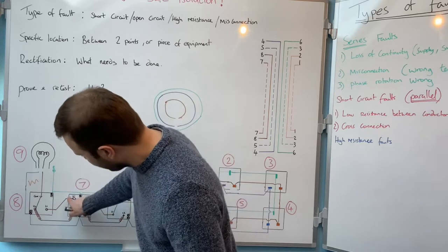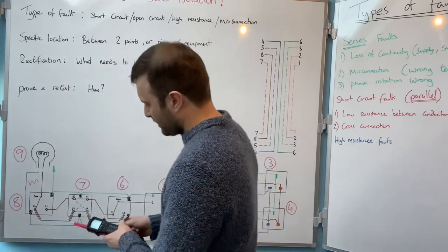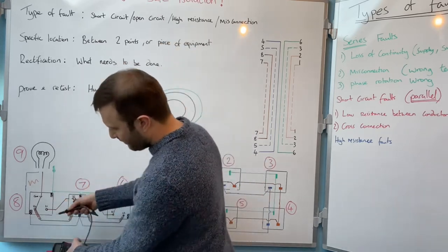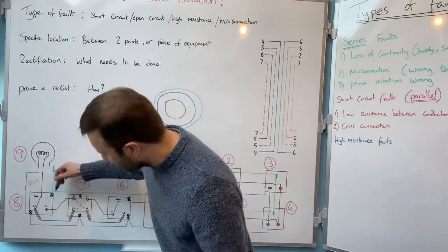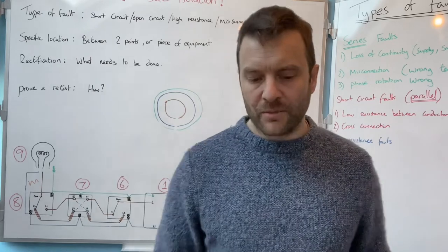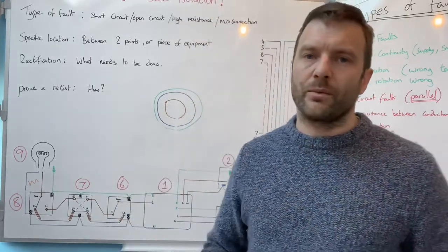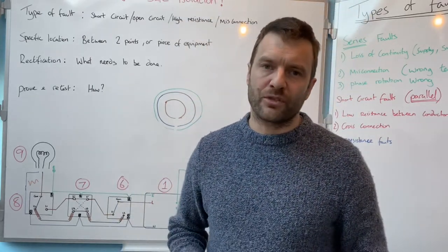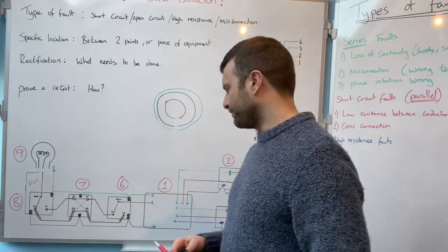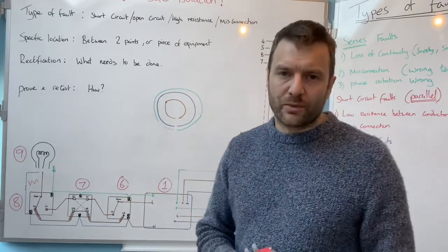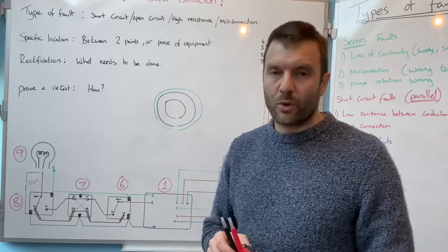I could then take the live out of this switch, test between live and neutral, no fault, and it's basically just a process of elimination. Sometimes you'll get lucky and you'll find it straight away, other times you won't, and you'll be scratching your head trying to find it. Fault finding is just one of those things, guys. There is no quick route.